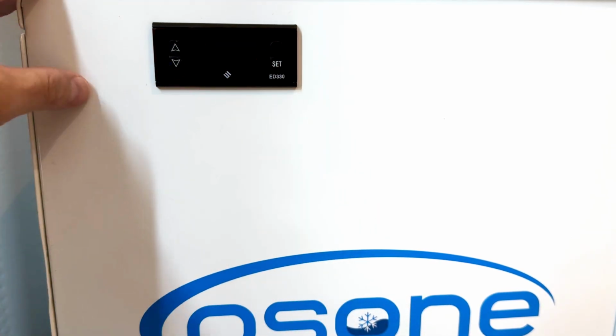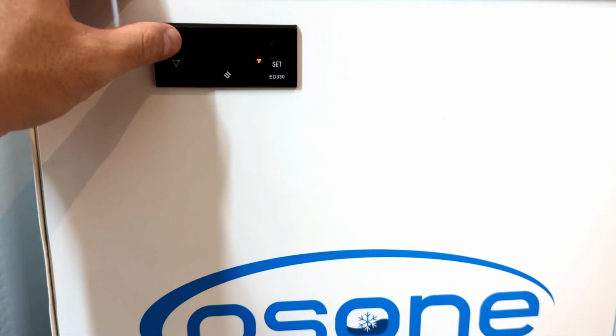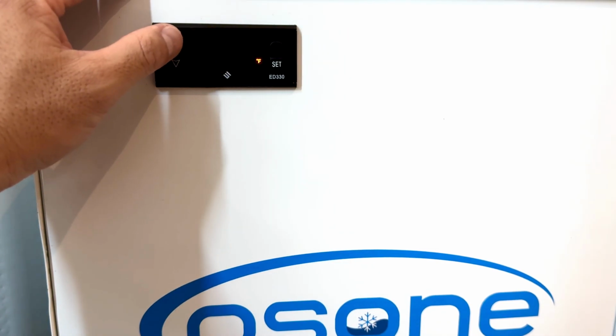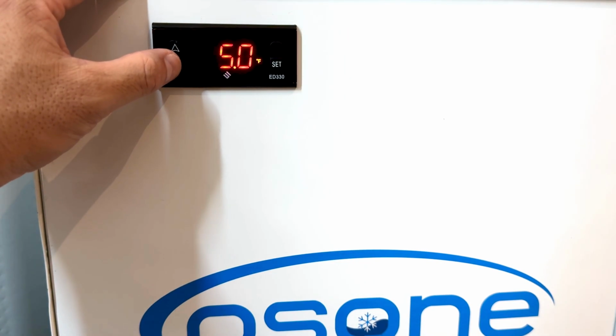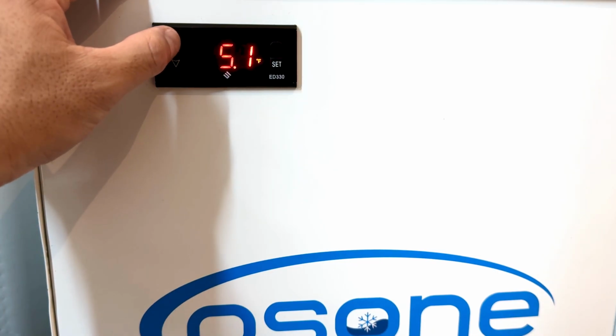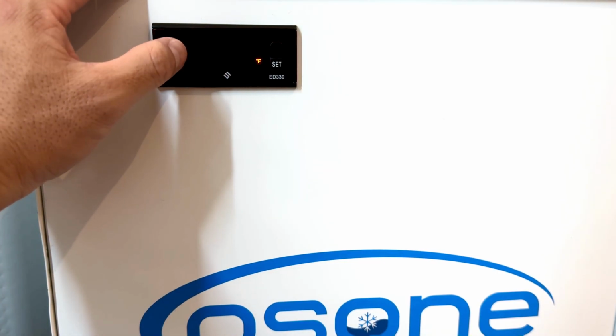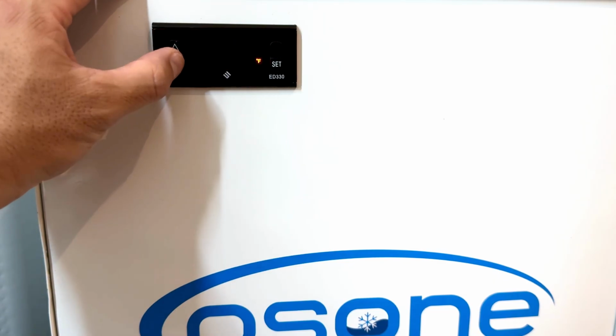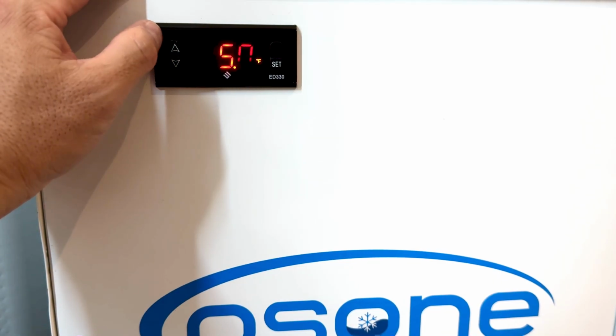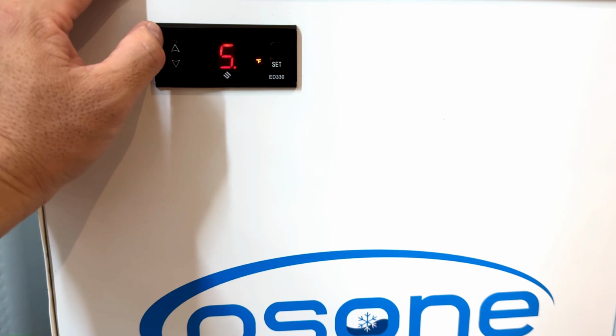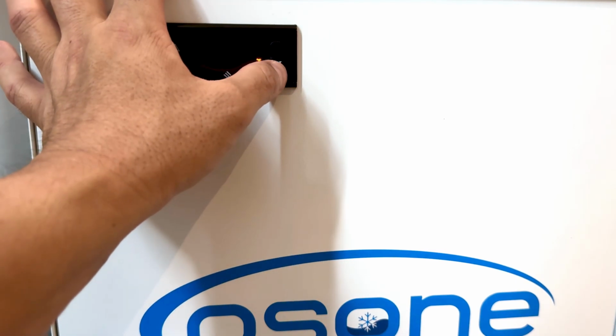You'll hit set again. Your E3 setting is the most important setting. This is when your compressor will turn off once it hits the set temperature, and when it'll come back on once it hits a temperature 5 degrees above the set temperature. This is very important so that you're not short cycling your compressor.